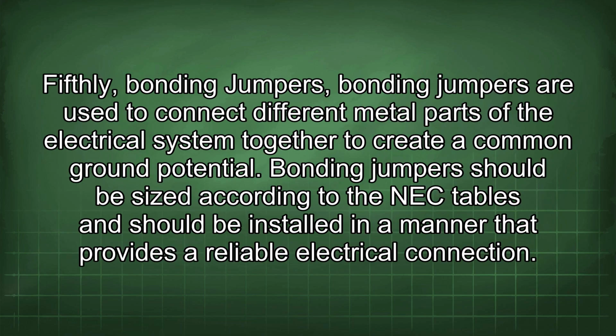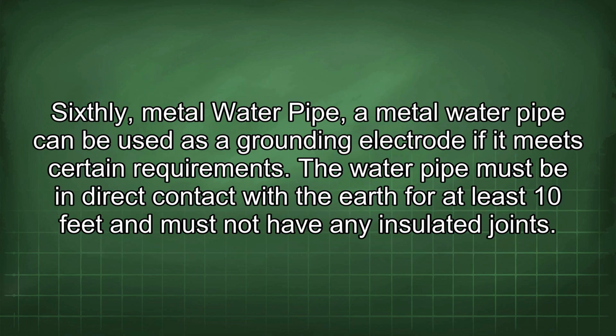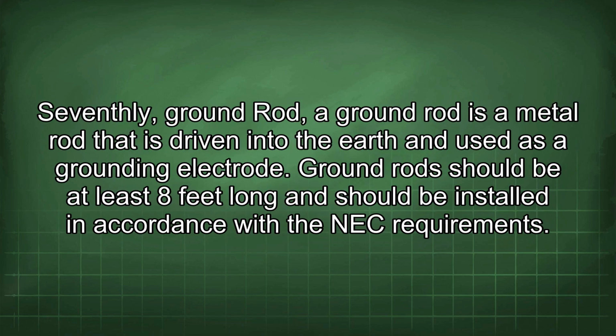Fifthly, bonding jumpers. Bonding jumpers are used to connect different metal parts of the electrical system together to create a common ground potential. Bonding jumpers should be sized according to the NEC tables and should be installed in a manner that provides a reliable electrical connection. Sixthly, metal water pipe. A metal water pipe can be used as a grounding electrode if it meets certain requirements. The water pipe must be in direct contact with the earth for at least 10 feet and must not have any insulated joint.